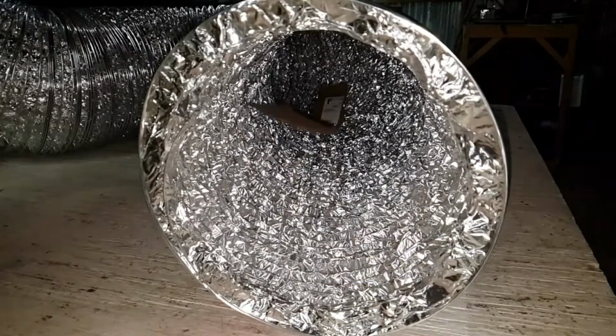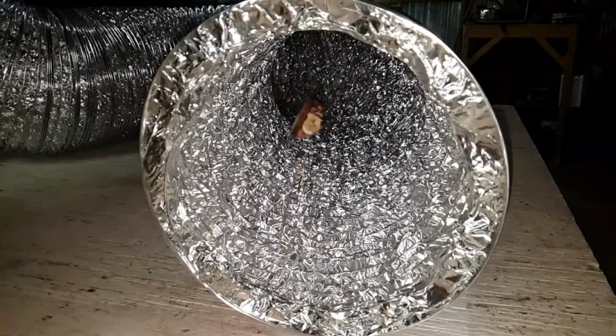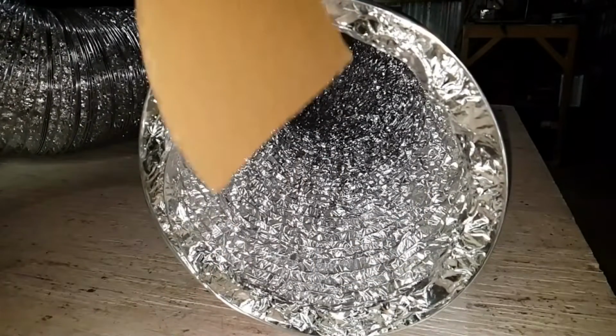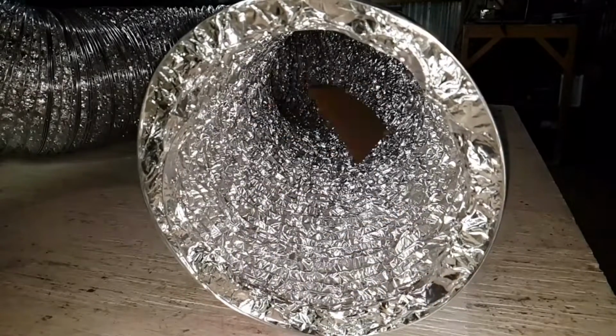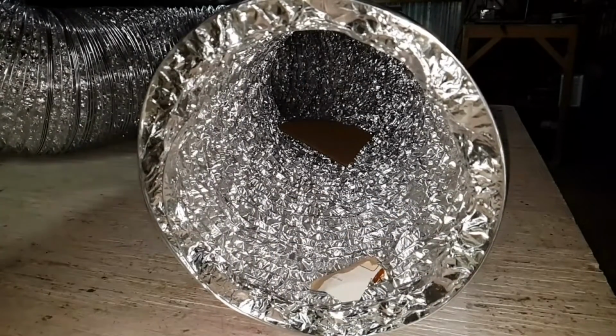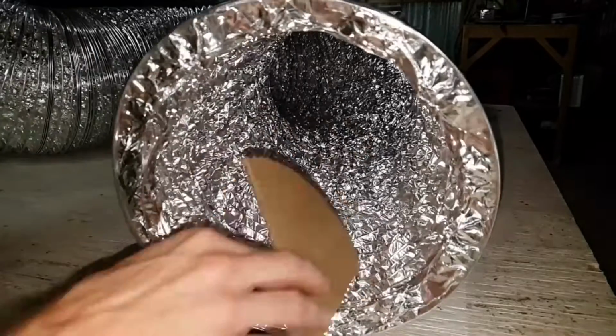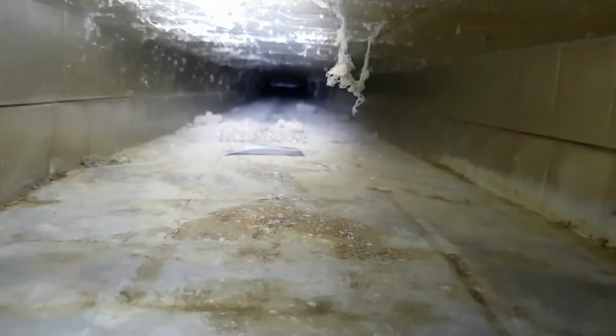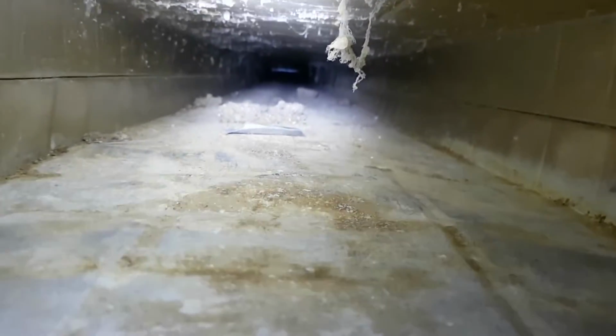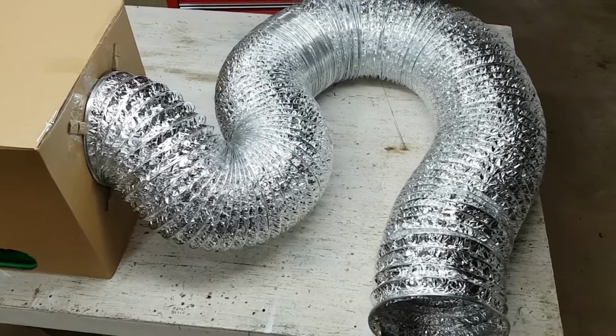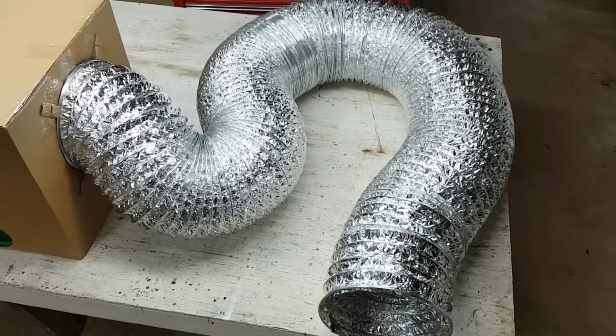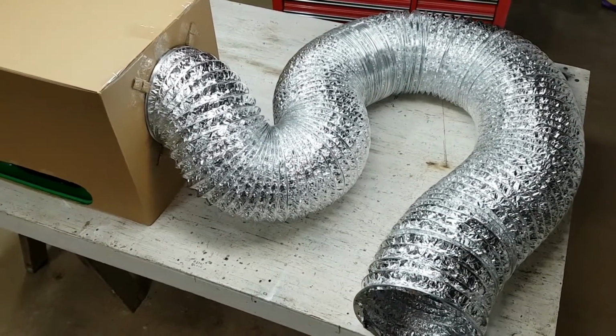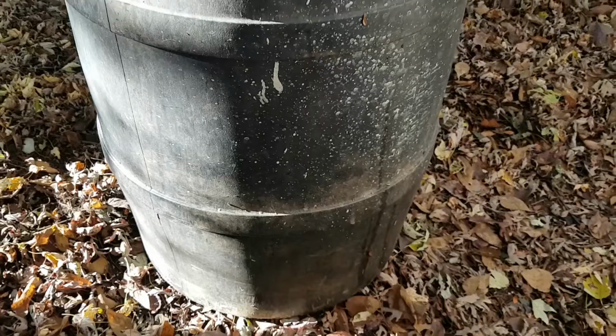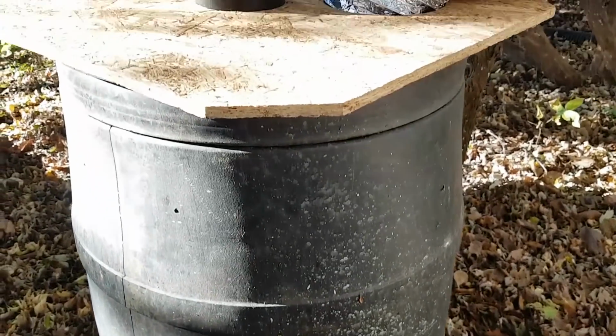The velocity of the air moving through the 12-inch duct will be lower, which is likely to result in more debris stalling and getting stuck in the vac hose. But it could deliver a higher volume of airflow, which I assume will raise the velocity of the air moving through the ducts in the house. I believe that's more important than the speed of the airflow through the vac hose, because I'd rather debris stall and get stuck inside the vac hose than in the HVAC ductwork. Too long of a hose can negatively affect the airflow as well.